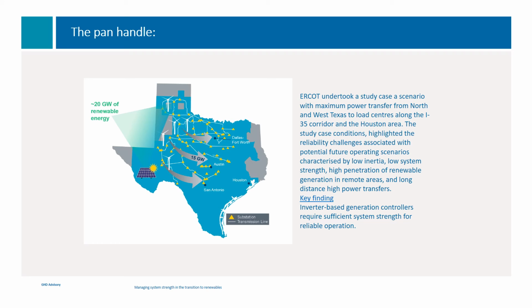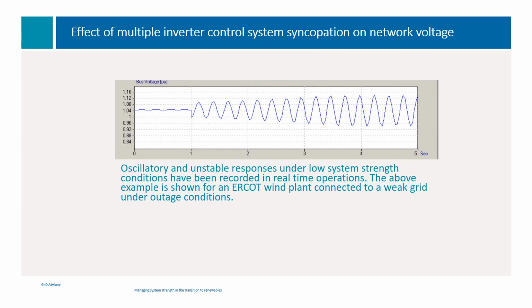Key findings were inverter-based generation controllers require significant system strength for reliable operation. This is one of the plots that they showed me, which is roughly a 6 Hz modulation on the mains voltage arising from a network disturbance that triggers a synchronous operation between inverters. As I mentioned earlier in my slide, because the inverters operate in an uncontrolled manner to a system disturbance, one tries to correct the disturbance, the other then overcompensates and so on. There tends to be a roughly 6 Hz modulation on the voltage waveform which is undamped, and as you can see here, gradually increases in amplitude until it reaches the extremes of the voltage limits on the network.